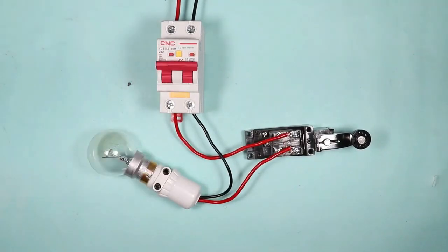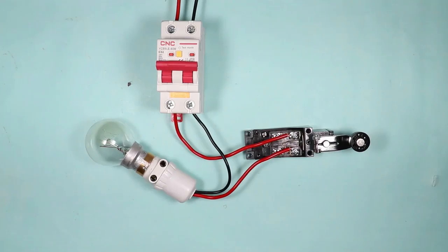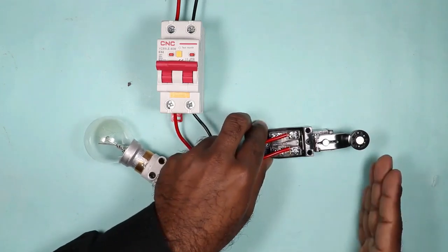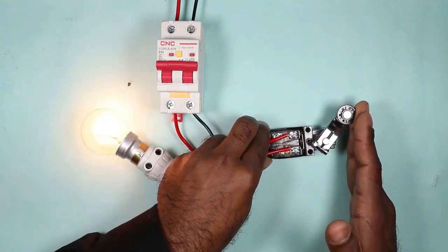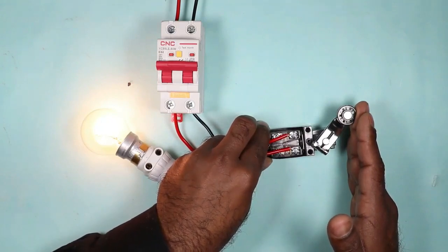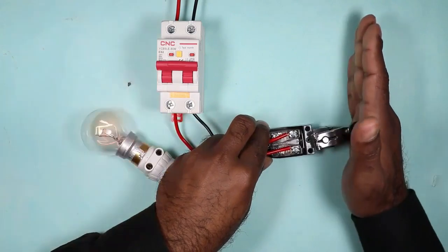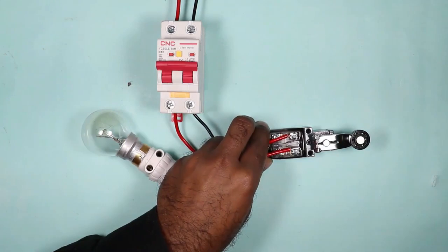On turning on the MCB, you can see the lamp is not glowing. This lamp is in off condition because the connection is in NO contact. Let's assume this switch is mounted with a conveyor belt. This means the object which is coming will touch this switch. When it touches the switch, then contact will change in the switch and the lamp will start glowing. This means now the limit switch is generating an output command. When the belt releases the switch, then the limit switch comes back to original position and our lamp will turn off.